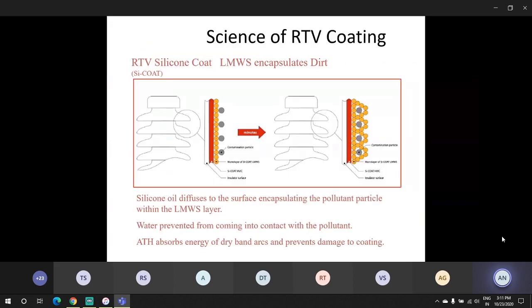So in short, the science of RTV coating is that silicone oil diffuses to the surface, encapsulating the pollutant particle. Water is prevented from coming into contact with the pollutant. The filler, whether it is ATH or quartz, absorbs the energy of the dry band arc and prevents any damage to the coating. So this is the summary of the science. Water cannot combine with the dirt, and therefore the surface is kept dry, and there is no electrical discharge activity or corona activity on the surface of the insulator.